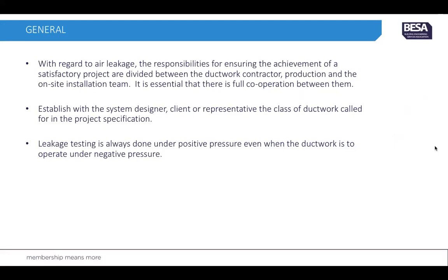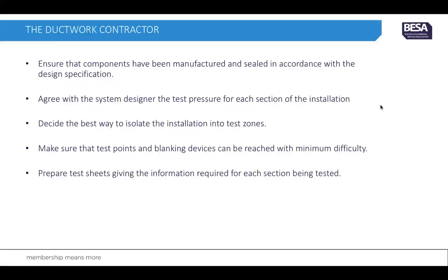It's essential that there is full cooperation between them. You need to establish with the system designer, the client or their representative, the class of ductwork called for in the project specification. You also need to know that leakage testing is always done under positive pressure, even when the ductwork is operating under negative pressure.